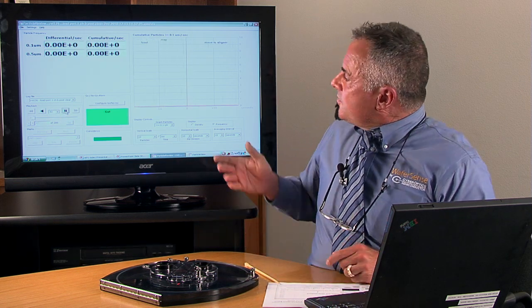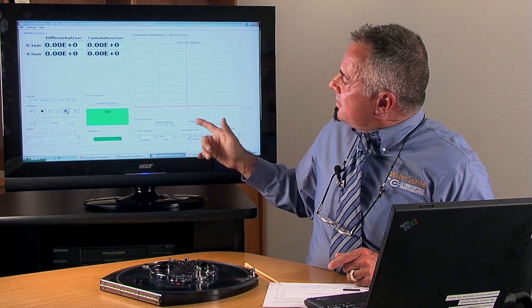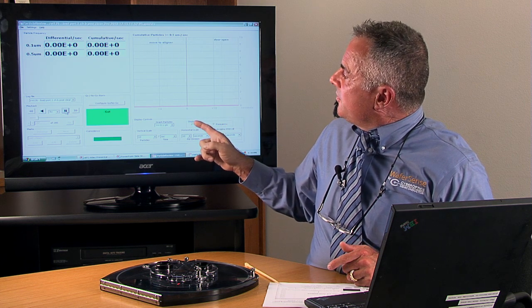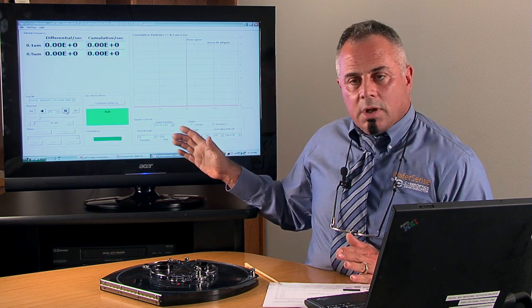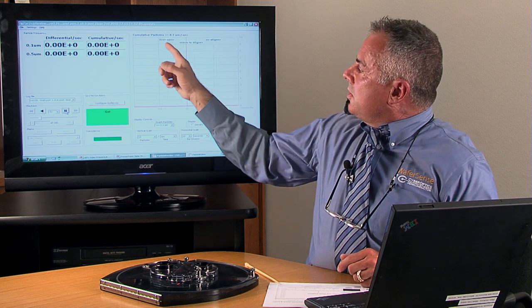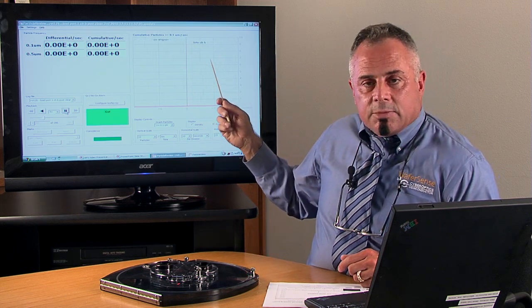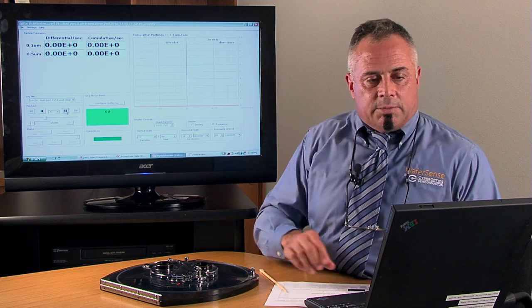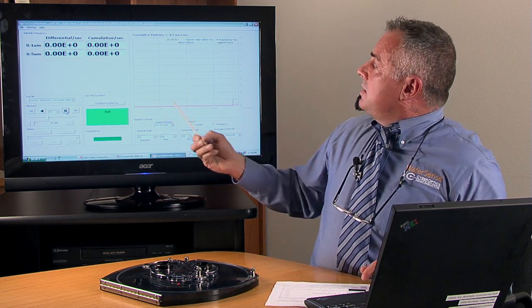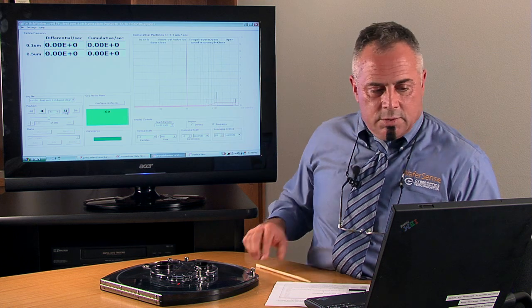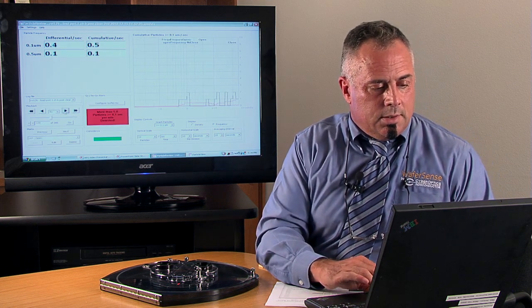So I've loaded the particle file from one of our tool qualifications. Here, door, open door, move aligner into chamber A, chamber B, etc. I have it running pretty fast here. But you can see, in this case, very few particles. Until we get to this chamber, we've discovered some particles showing up.